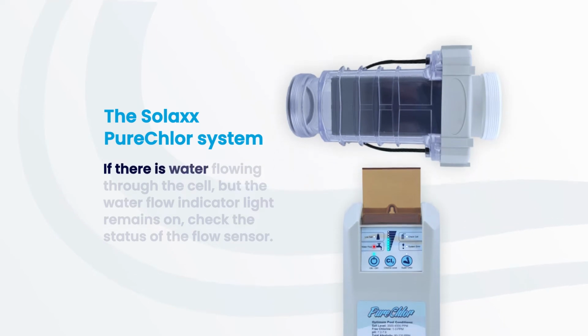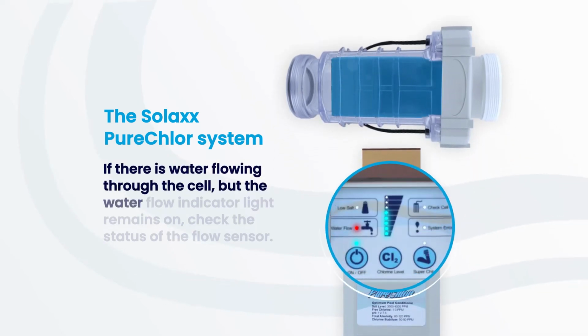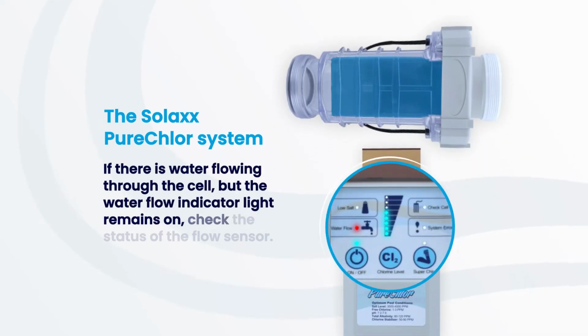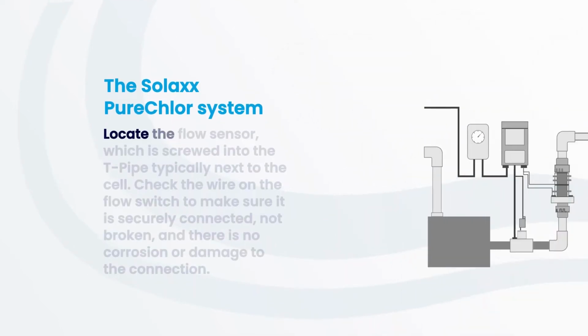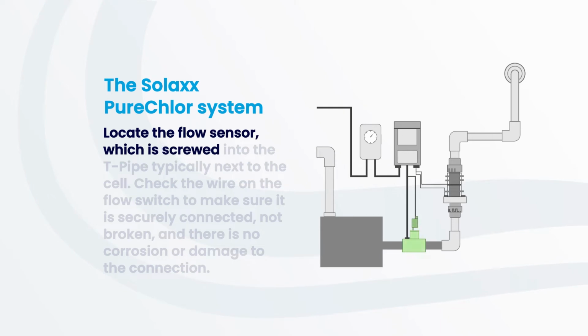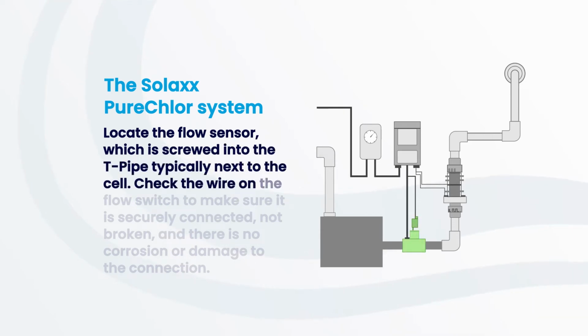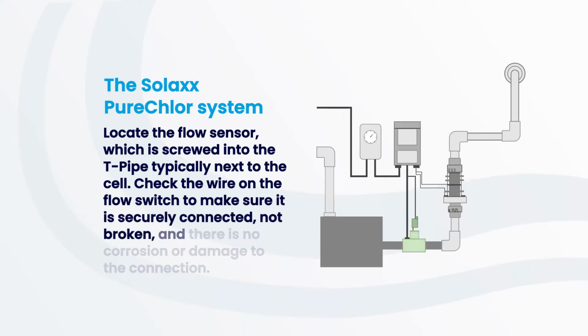If there is water flowing through the cell, but the water flow indicator light remains on, check the status of the flow sensor. Locate the flow sensor, which is screwed into the T-pipe typically next to the cell. Check the wire on the flow switch to make sure it is securely connected, not broken, and there is no corrosion or damage to the connection.